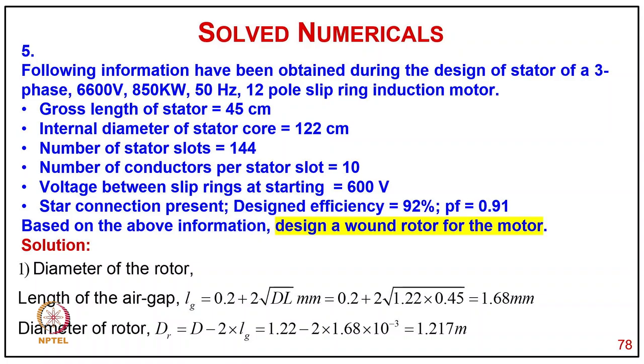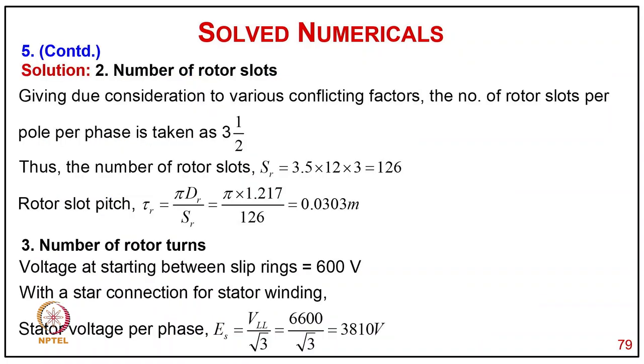So, length of the air gap, L G equals 0.2 plus 2 times root D L, so it comes to 1.68 millimeter. So diameter of rotor is D R equals D minus 2 L G, it comes to 1.217 meter. Now coming to number of rotor slots, giving due consideration to various factors, the number of slots per pole per phase is taken as 3.5.